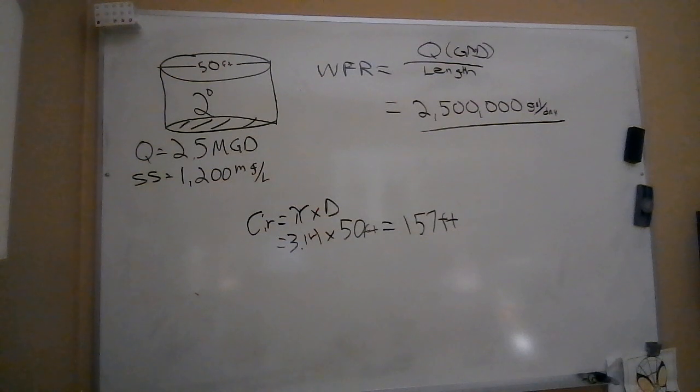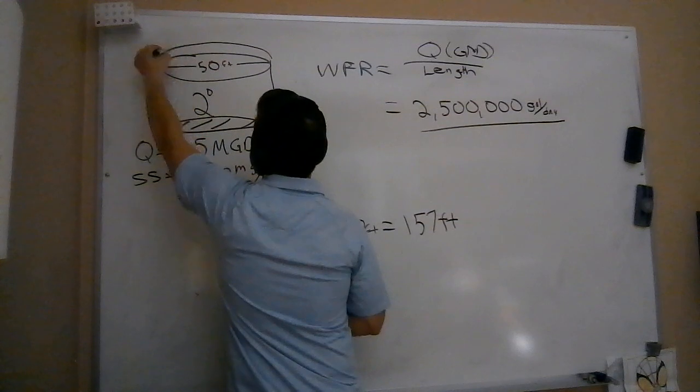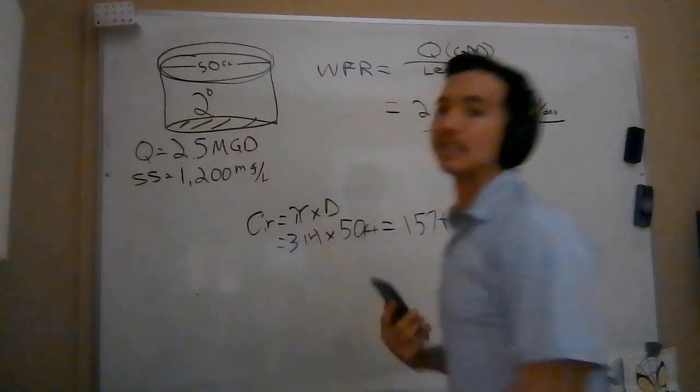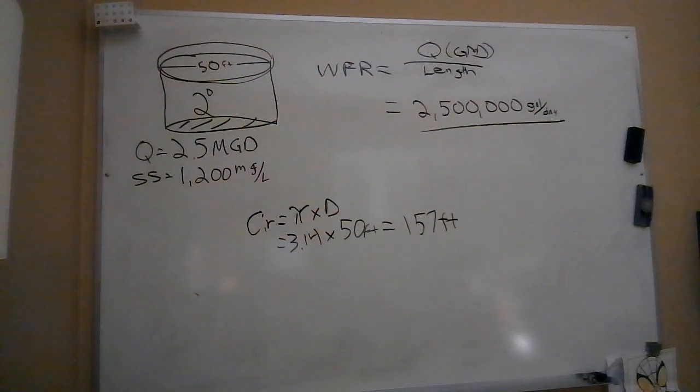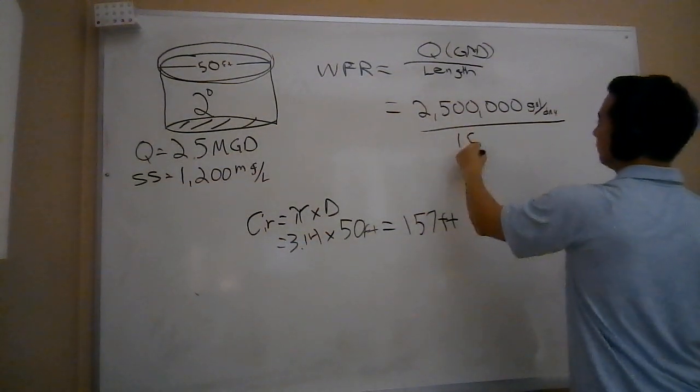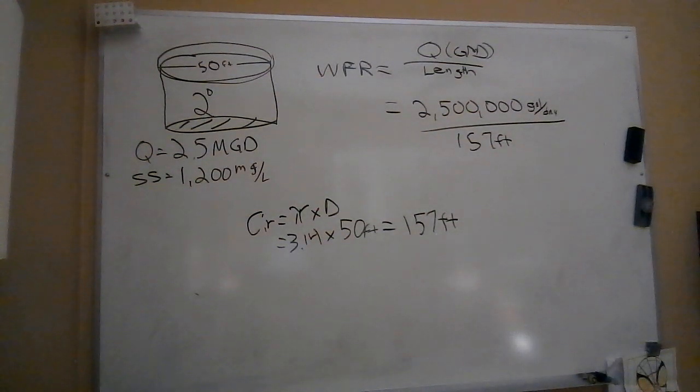Imagine you're on the outside here, walking around the outside in a linear fashion to get the length of that weir. The reason we use a weir is it helps to elevate and stabilize that flow - we want nice uniform flow coming out of our clarifier into that trough where we're capturing that water on its way to tertiary treatment. So the length here is 157 feet. Now I'm just going to divide it out: 2,500,000 divided by my 157 feet of weir length.